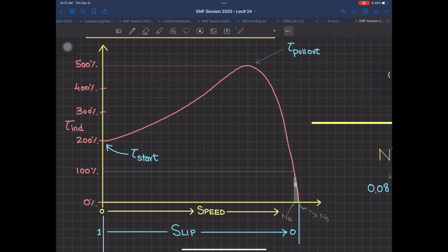And this is the main reason that the induction machine has overthrown the series motor from very critical loads, such as lifts, elevators, or something on the cranes. Previously the series motor was used, the series DC motor I'm talking about, because it was having a very good starting torque. Now the induction machine is the actual answer, and the advantage is enormous. First of all, you only have to give one supply to the stator. In the rotor you don't have to give supply. You are going to get something in the 80 to 85% efficiency range also. Efficiency is also increased.